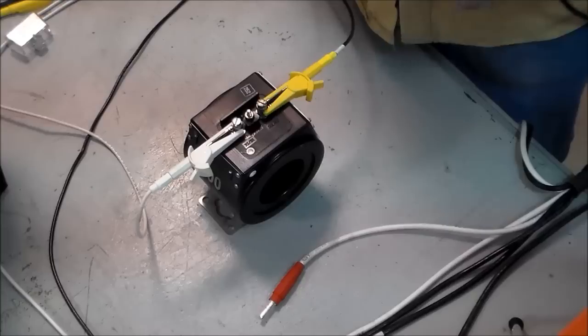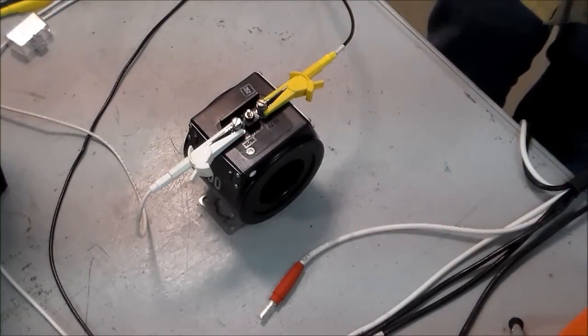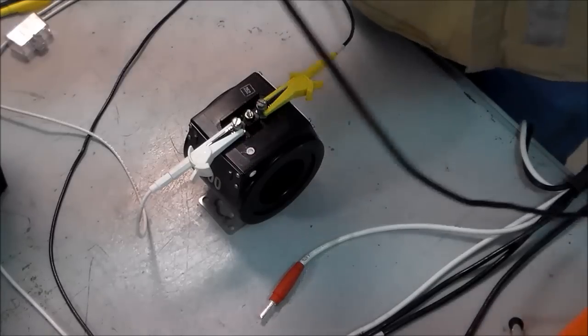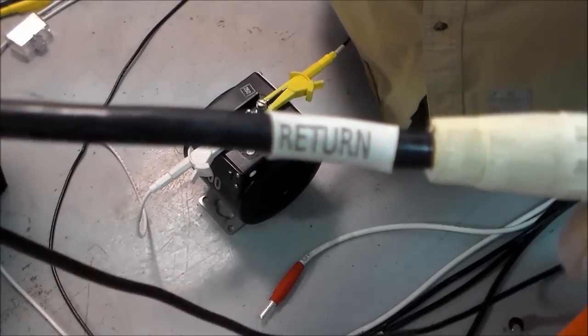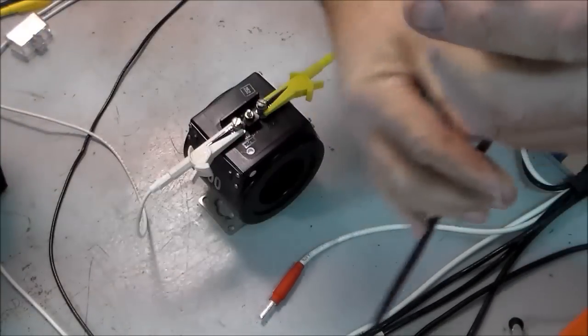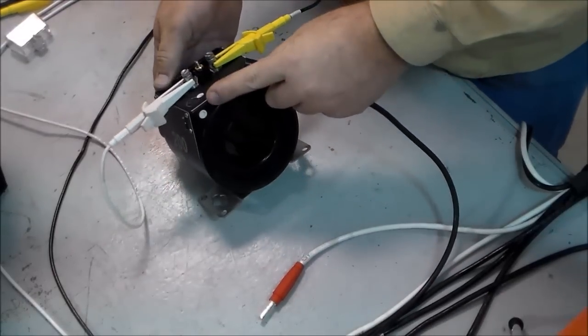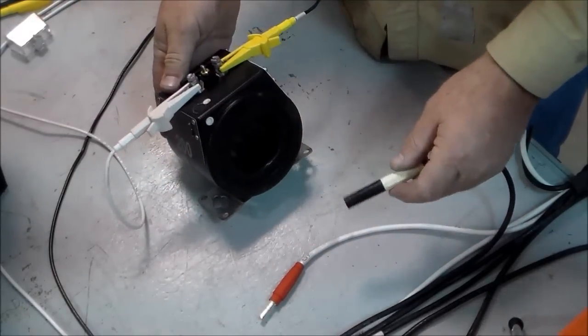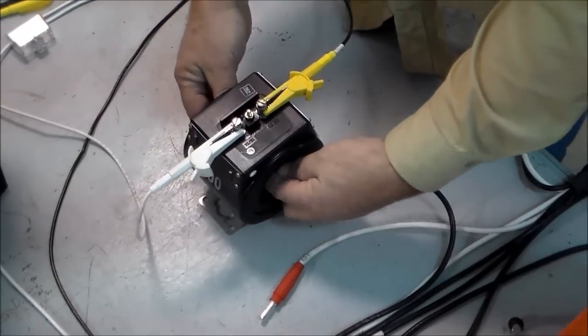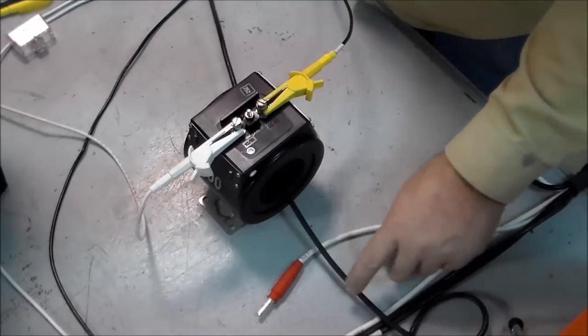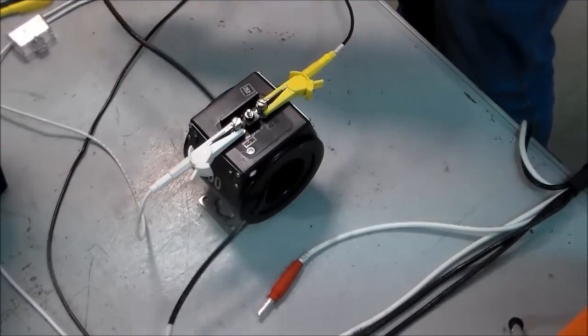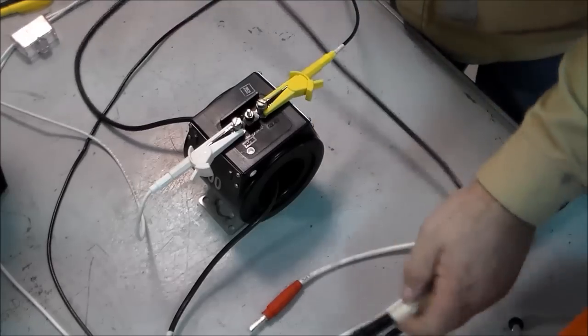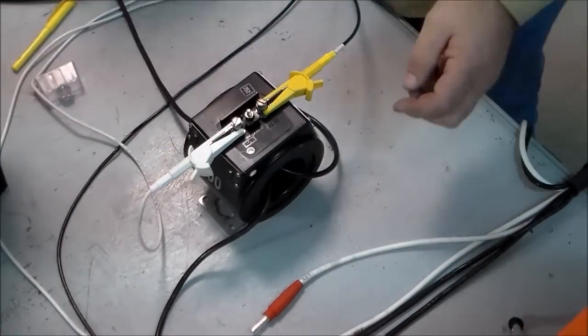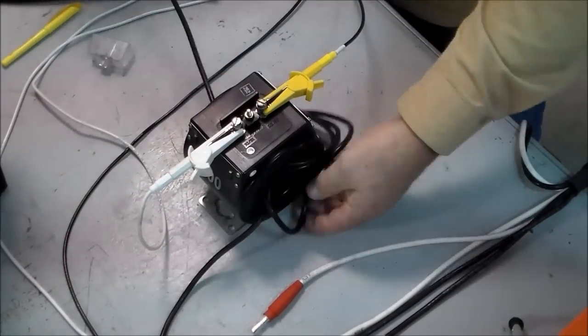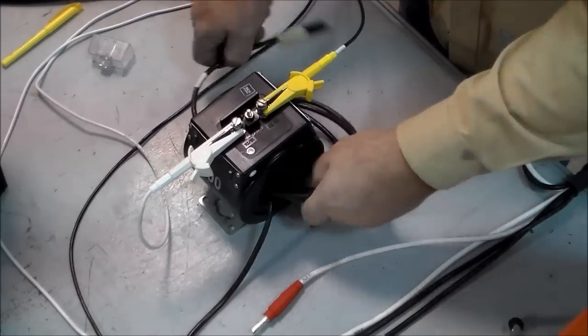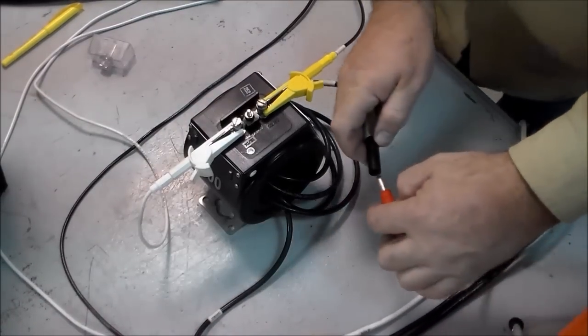Now you'll have to think of this just like you would on the job. Your current is being driven. It's going to come from the source on the polarity side. So you'll actually insert the return lead in first, and you can loop it through once or as many as 5 times. Once you've selected your turns ratio for the drive cable, connect it to the A-phase current lead labeled return.